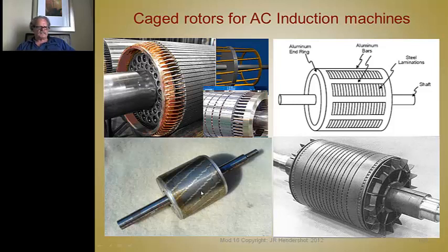Now this is very interesting. I referred to this before. Here, this is one bad die casting job. That would be scrapped. You see, this is the alignment of the laminations when they're skewed in the tooling, so bad that you've got places here where you can't even get the current to flow through because it's offset, misaligned so bad that you completely blocked off the aluminum there. There might be just a paper thin connection between this part of the bar and that part of the bar, which is going to be a very high resistance point. So that's very critical. You want to avoid that.